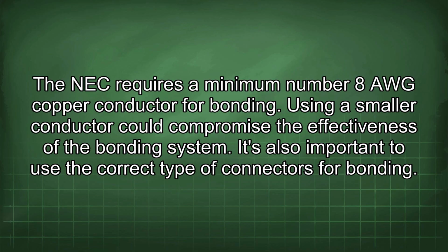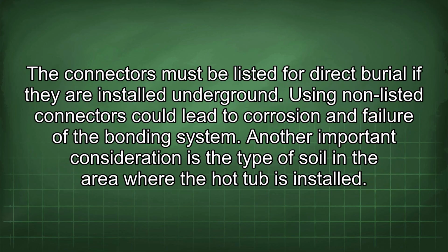Using a smaller conductor could compromise the effectiveness of the bonding system. It's also important to use the correct type of connectors for bonding. The connectors must be listed for direct burial if they are installed underground. Using non-listed connectors could lead to corrosion and failure of the bonding system.